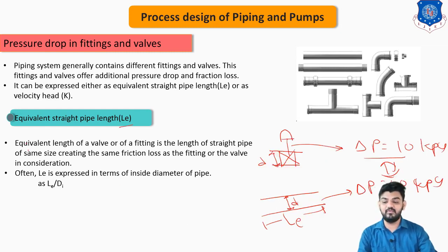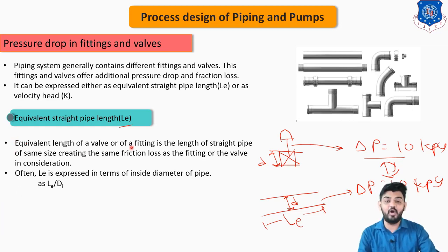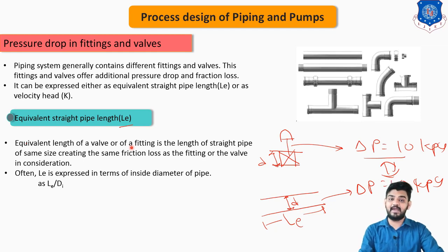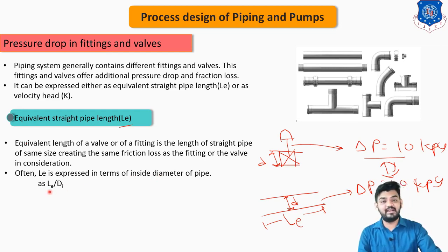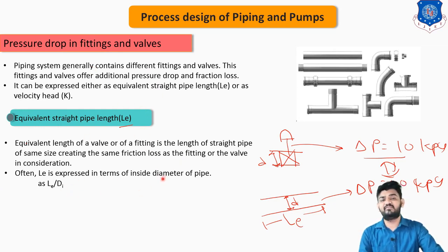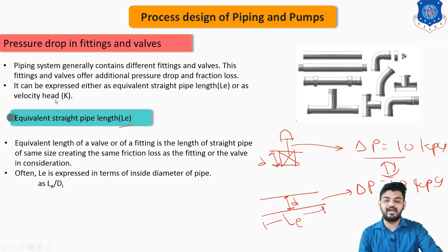This equivalent length is also expressed in terms of the inside diameter of the pipe as equivalent length divided by inside diameter — Le/Di. That is one way to express the pressure drop from fittings and valves. Another way is the velocity head, represented by capital K.